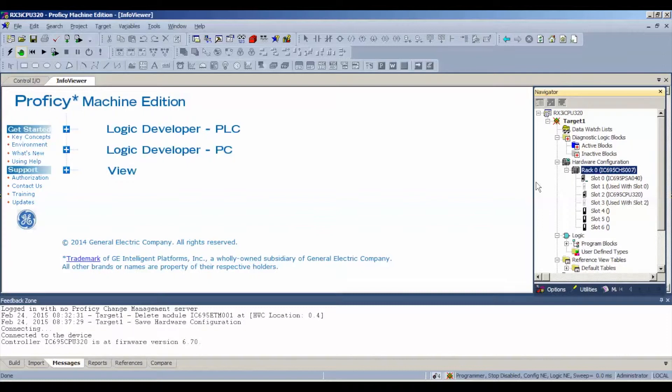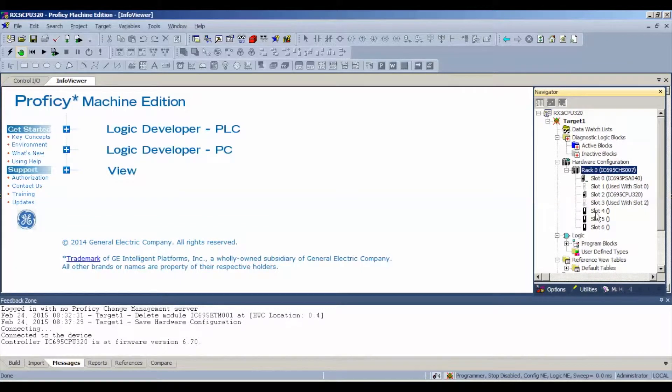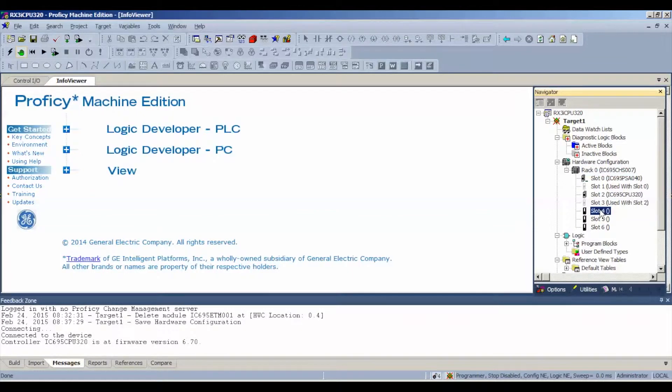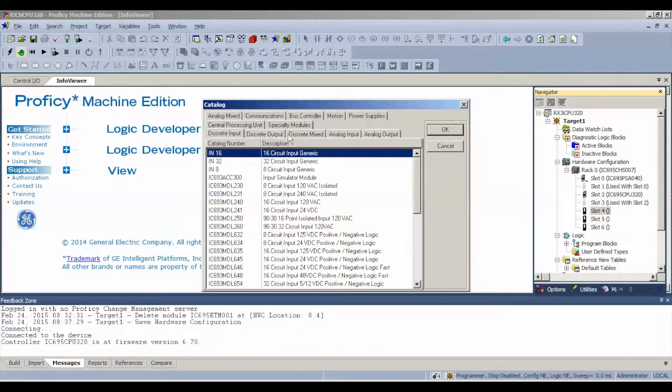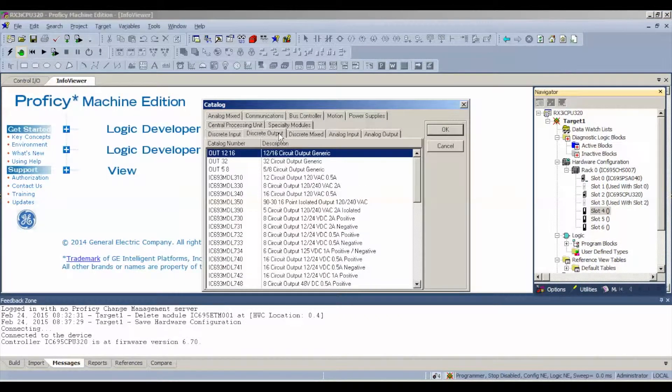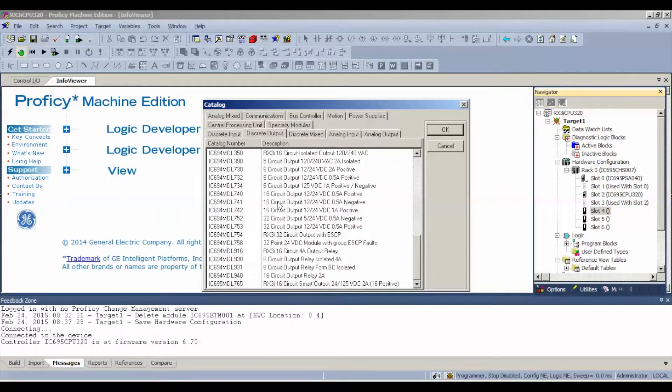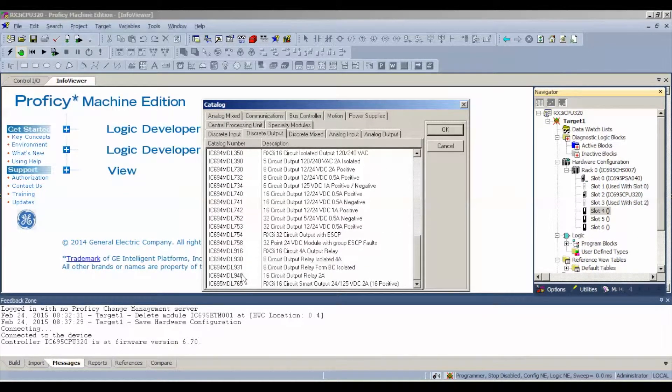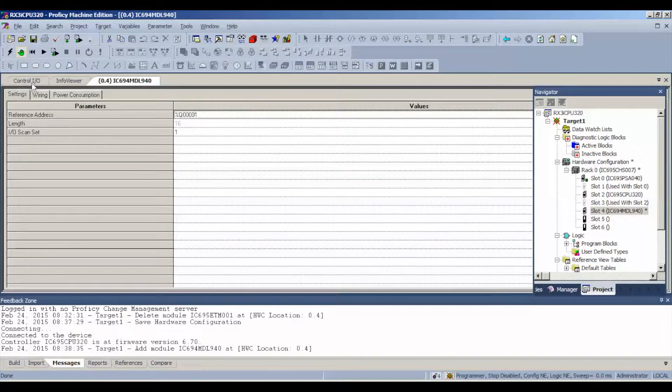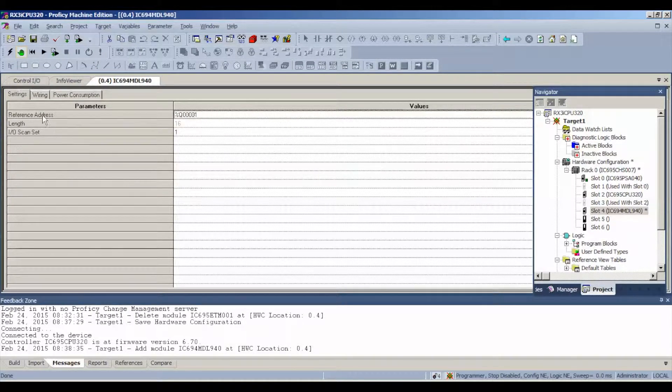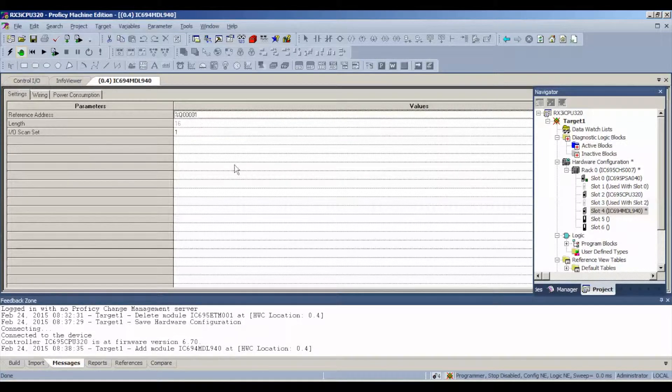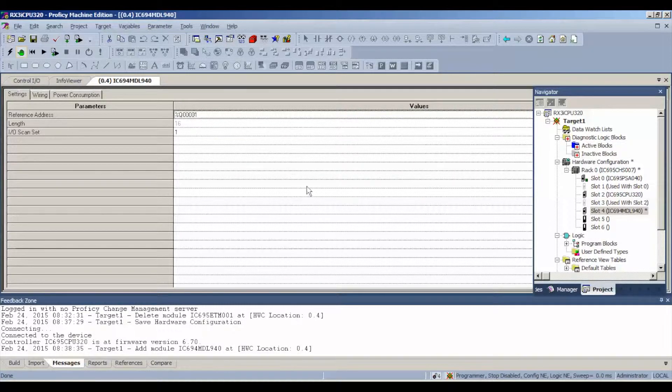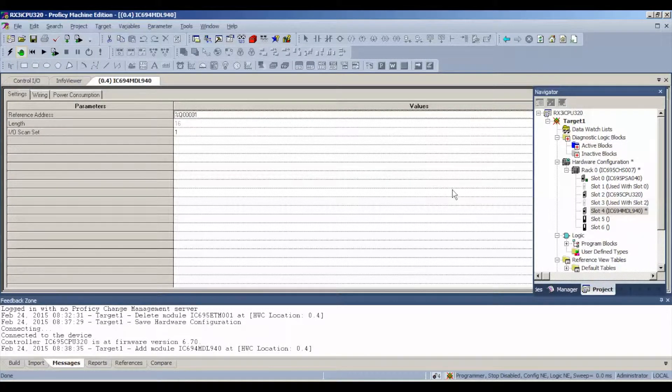In slot number 0 and 1 is my PSA040 power supply. It's using two slots. Slot number 2 and 3 is my CPU320 using slots 2 and 3. It leaves me with slots 4, 5, and 6 open. Slot 4, if you right click or double click and hit add module, go to discrete output and nearly the bottom selection you'll see the IC694MDL940. There's no settings per se on this but what you do want to note is the reference address so that when we go to the output table you know that it's output 00001 for channel 1 and then subsequently after that all the other 16 channels will follow. Channels 0002, 3, 4, 5, 6, and so on.